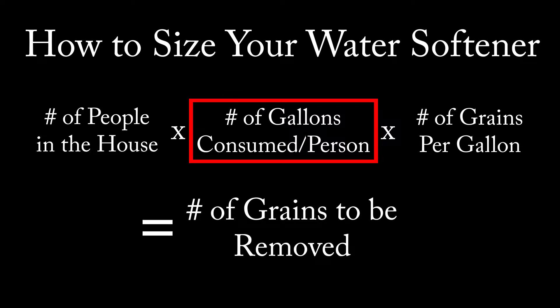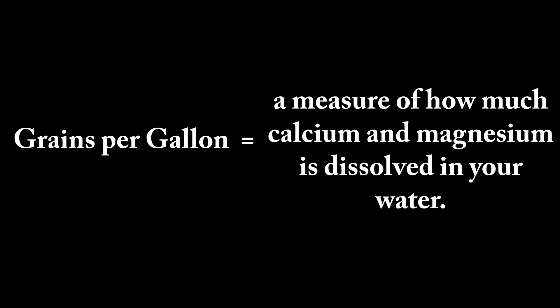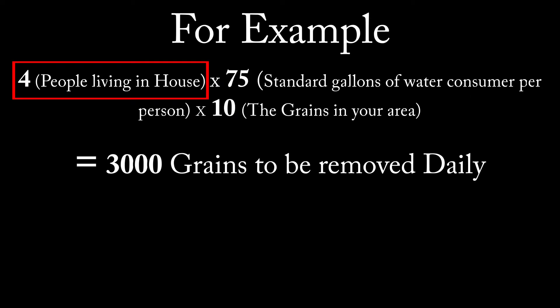For the number of gallons consumed per person, you can use 75 gallons, which is the national average. And for grains per gallon, you can call your municipality if you use city water, or purchase a water test kit if you use well water. Grains per gallon is a measure of how much calcium and magnesium is dissolved in your water.